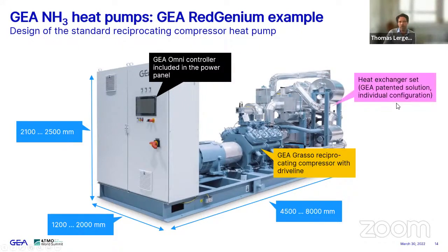And here in the back, you see the heat exchanger set that includes some nice gimmicks, a GEA patented solution with a very efficient, compact evaporator-separator combination. On the hot side, it provides a very project individual configuration of each heat exchanger that's also very important for the overall efficiency of the heat pump.